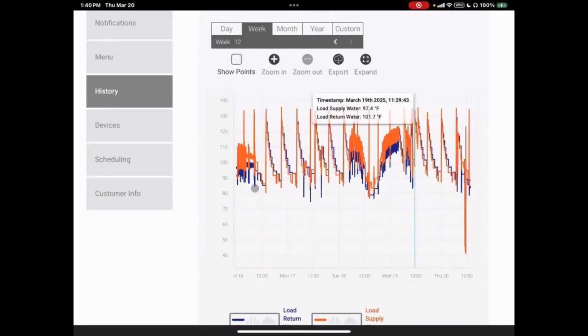But you can see we've mainly been heating in here, and you can see these kind of larger filled in areas. This is when we had pretty cold temperature, and you can see a spike of a domestic hot water call in there. But when you see these kind of tapering off and tapering up, this is outdoor reset. So this is our target water temperature rising as it gets colder outside and then falling the next day when the sun's up. And then these high spikes in between are our domestic hot water calls.